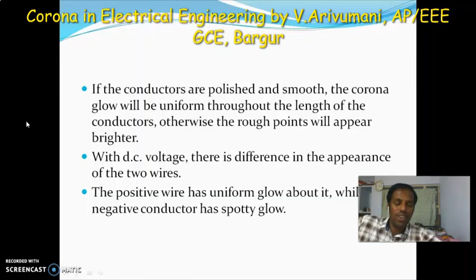So what is the theory about the corona formation? I already told you that ionization takes place in the phenomenon of corona. Some ionization is always present in air due to cosmic rays, ultraviolet radiations and radioactivity. So the X-rays, cosmic rays, UV radiations and radioactivity are normally present in the air. So in normal conditions, the air around the conductors contains some ionized particles and neutral molecules.